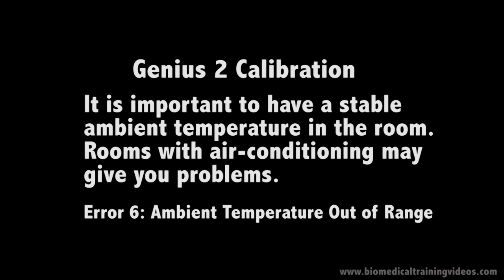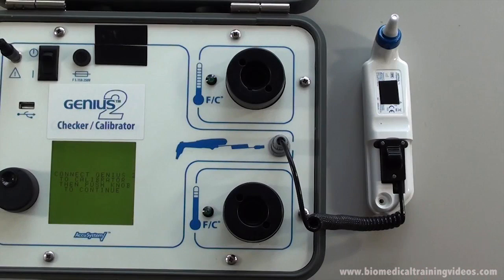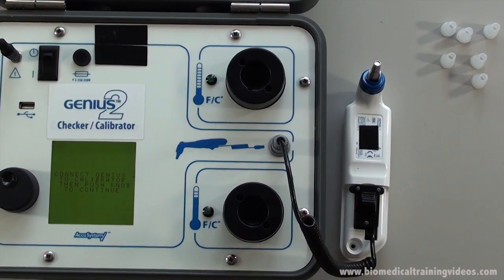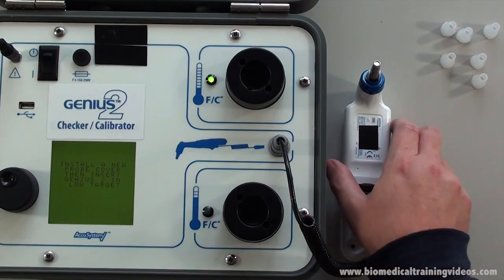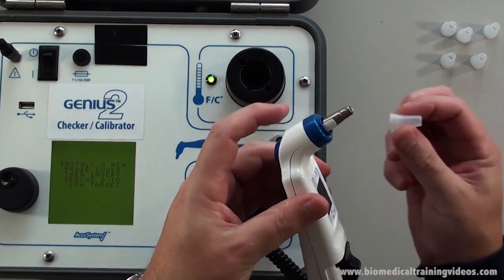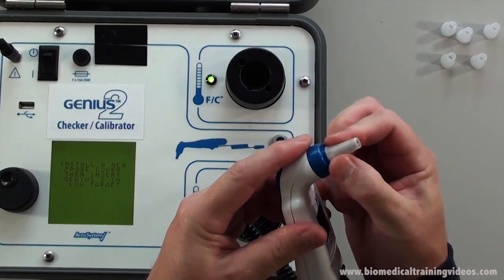So it's important to make sure you've got a stable ambient temperature when performing calibration. If you've got air conditioning in the room, it may give you some problems because the temperature is varying, and you will get an error 6, ambient temperature out of range error. So here we are, just going through the steps involved. We've connected the thermometer to the checker. We've got our probe covers in place, ready to go. So you've really got to make sure you're set up well in advance when doing this, and you need a bit of concentration as well, because there's a few steps to follow.